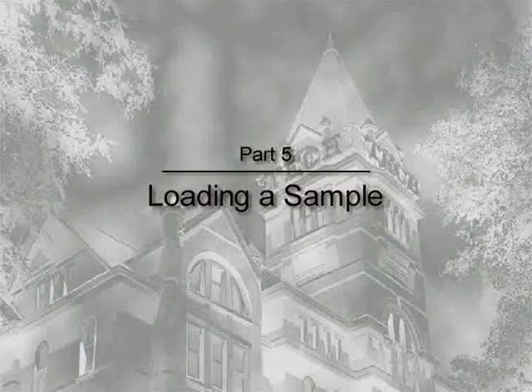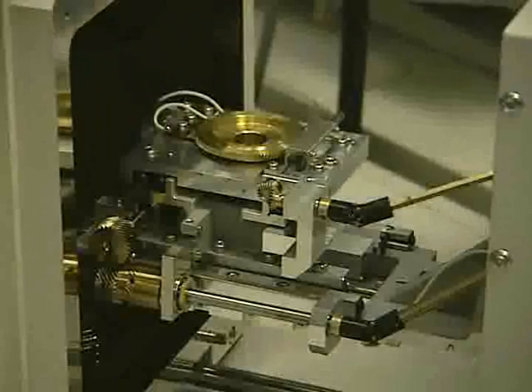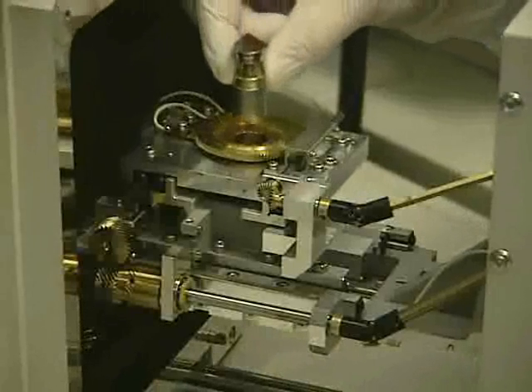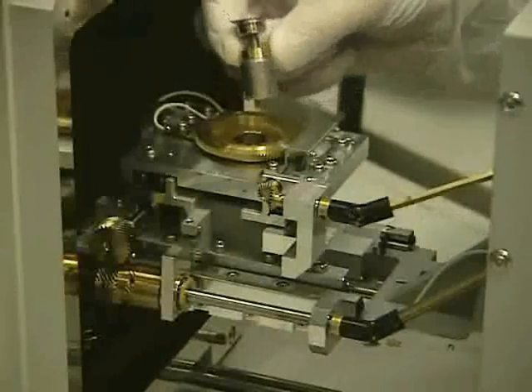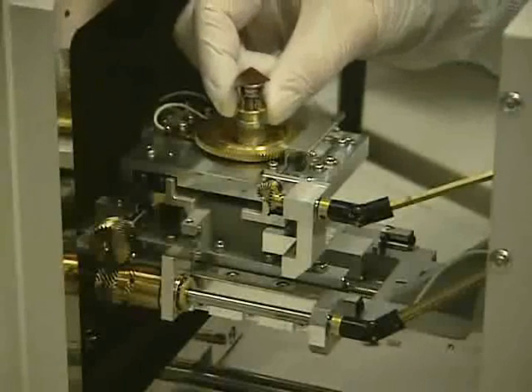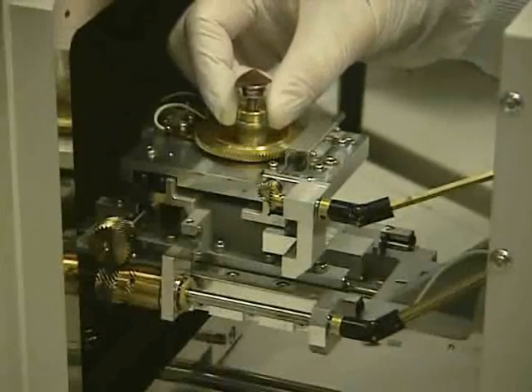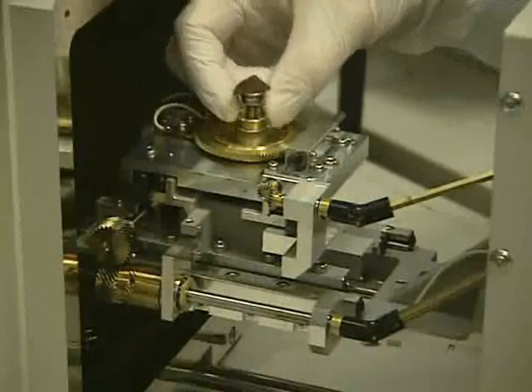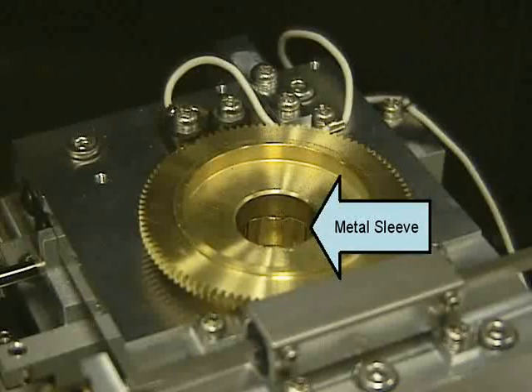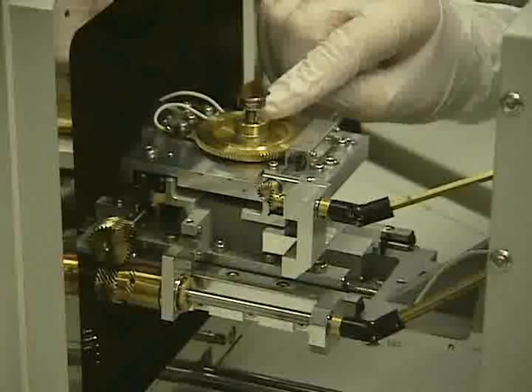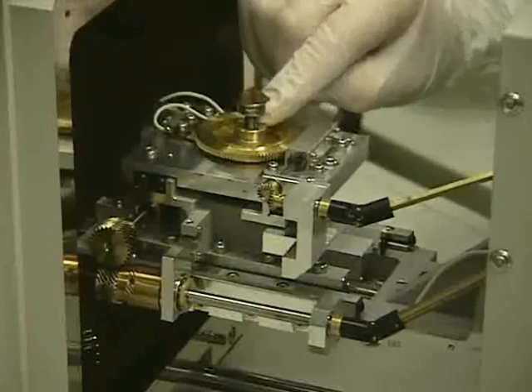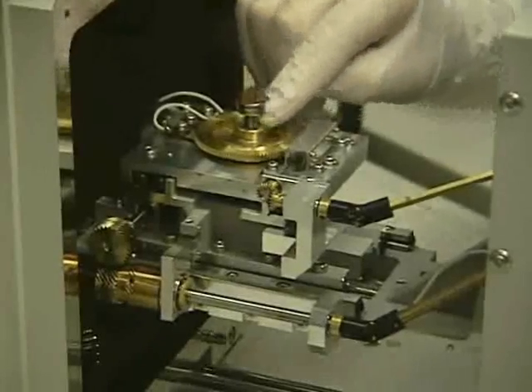Never pull on the chamber door. It will open by itself when it reaches atmospheric pressure. Carefully put the stub into the stage. Make sure to put the stub in straight. Do not tilt it. Put it in and gently slide it in. If you feel any resistance, do not force it. You can crush the metal sleeve inside the mounting hole. Make sure the stub is fully seated once you put it in.